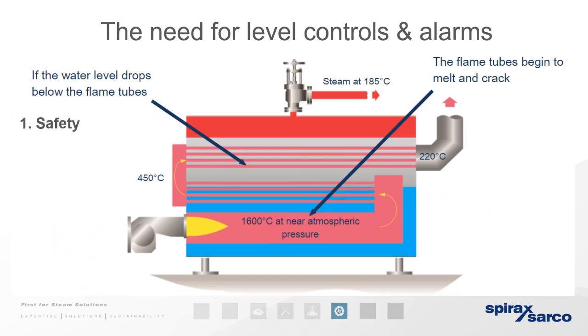So here you can see you have enough water covering the fire tubes. We want to cover this area here. If the water level drops below the flame tubes, this is when it becomes dangerous. The tubes begin to melt and crack, because the heat isn't transferred into the water and isn't dissipated. That's when there's a danger of collapse of the fire tube. So that's why level controls are very important to us. It's also because we want to get as much heat out of this as possible. If we're transferring it through the tubes, we want to capture that energy in the water, not just allow it to disappear.